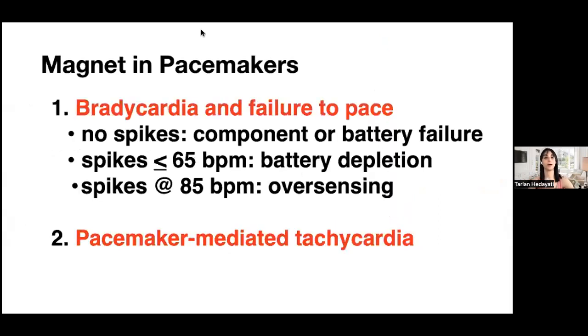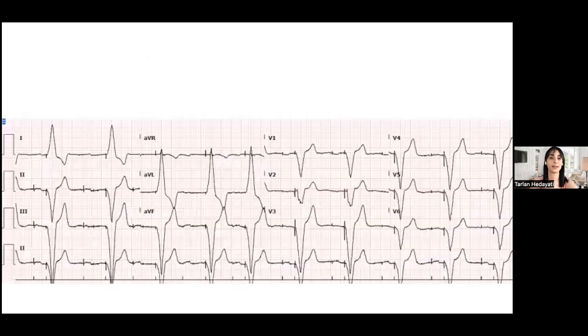So we talked a little bit about when you're going to use a magnet in pacemakers. We talked about bradycardia and failure to pace, and the three responses you'll get in that scenario: either no spikes, which means the pacemaker is dead; the spikes will be slow, less than 65 beats per minute, which tells you the battery is reaching the end of its lifespan; or it'll just reset back to its normal rate, meaning something had interfered with the pacemaker and now it should be fine once you put the magnet on. Pacemaker mediated tachycardia is another scenario where the magnet can be very helpful. So those are really the two scenarios where you'll end up using a magnet in a pacemaker.